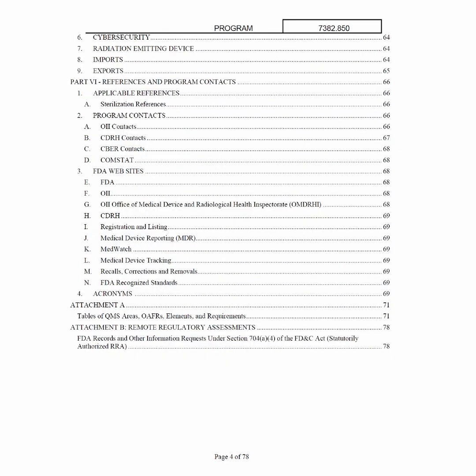This new inspection technique represents a significant shift in FDA inspections, moving away from the compartmentalized QSIT approach towards a total product lifecycle method. Under this change, FDA investigators are required to integrate post-market surveillance and lifecycle data into all aspects of their investigation. So what this really means is that things like complaint trends, medical device reports, recall trending patterns, servicing records, and supplier issues are no longer going to be reviewed in isolation.